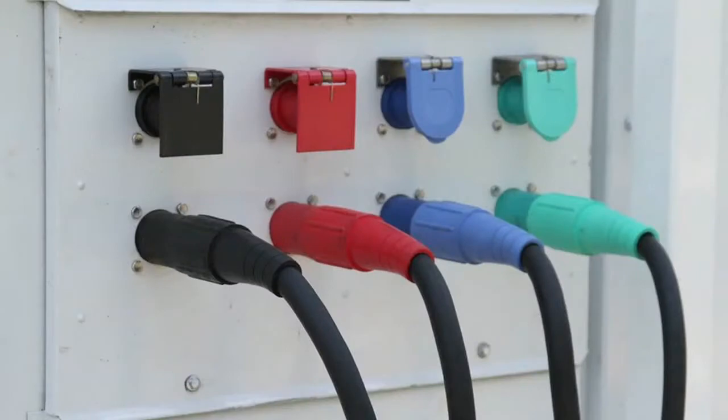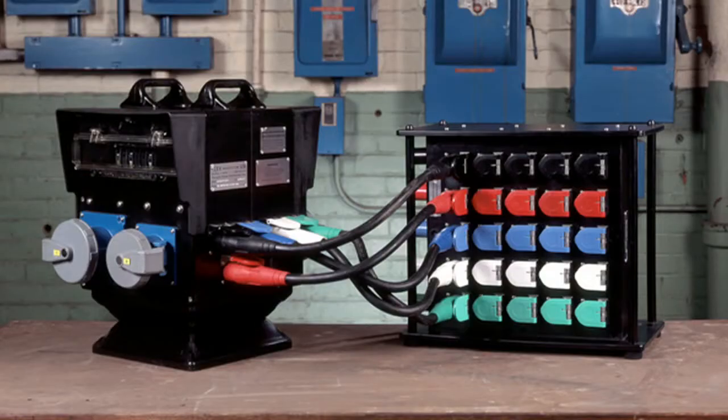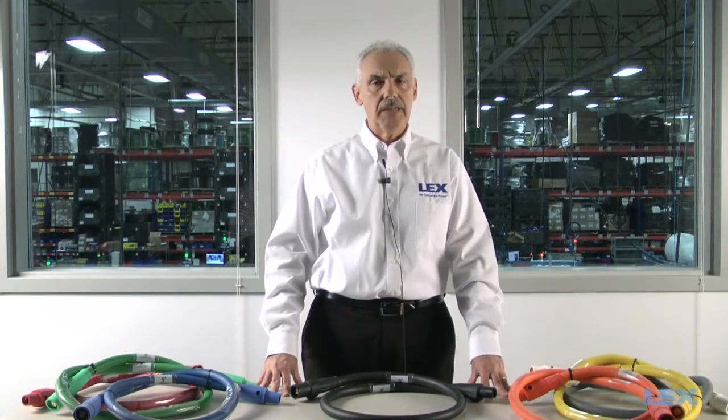Feeder cables are single conductor runs of cable that go from the power source to a distribution box or between distribution boxes. They are commonly the larger portable cables, with 4/0 AWG being the most common. These cables are typically single conductor because they are heavy — an all-in-one multi-conductor cord with an overall jacket would be too heavy and no longer be portable.